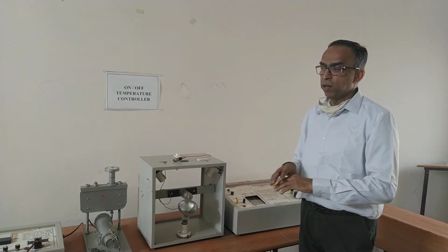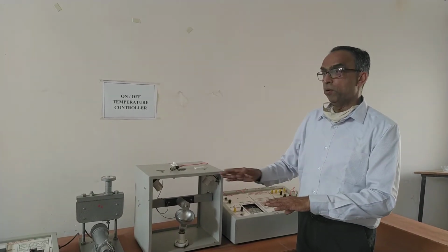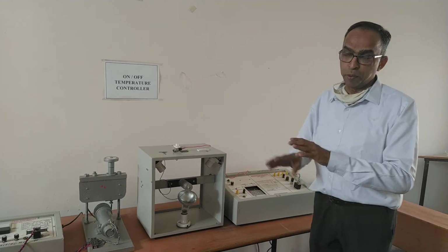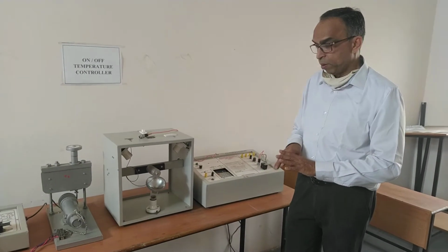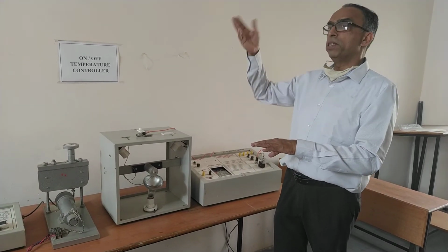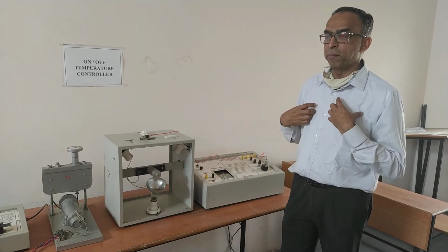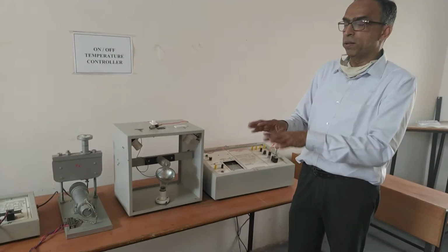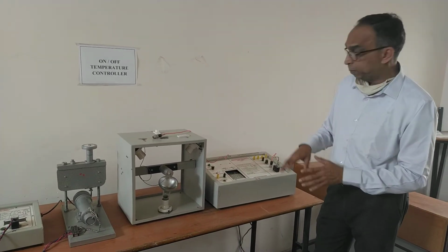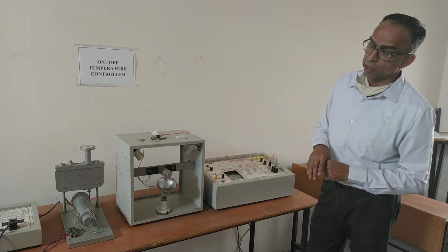Why is the proportional controller behaving like that? Because it is subjected to sudden load change. It responds to sudden load change by adjusting its own set point, which is not desirable, because even after removal of the sudden load change, that set point will remain shifted. That is not desirable, isn't it? Whatever temperature I want to maintain should be maintained. The set point should not be changed on its own. So that offset phenomenon can be studied by using this microprocessor based temperature controller, friends.